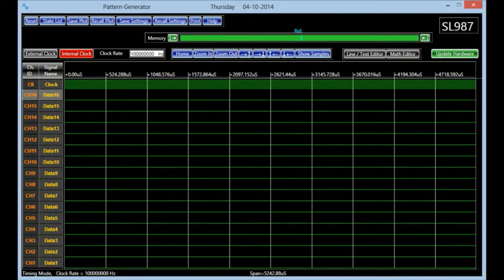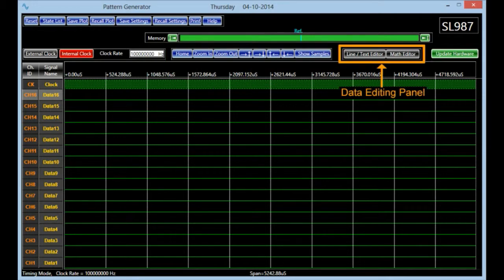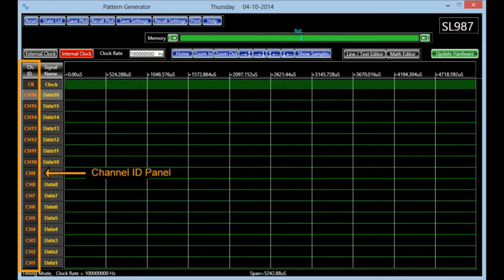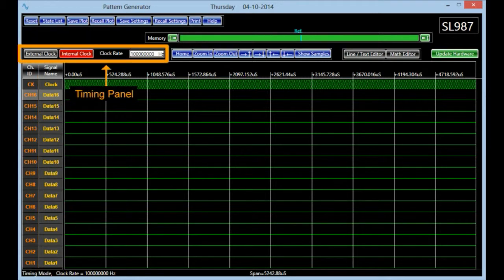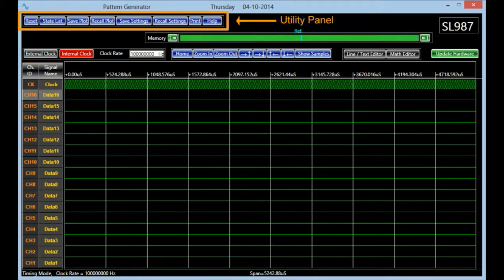In this instrument, the user controls are grouped together based on the function they perform. The display banner contains those controls which configure the screen plot. The data editing panel houses the controls used for bit editing. Besides these two panels, there are a channel ID panel, a signal panel, a buffer memory panel, a timing panel, and a utility panel. Each individual button in these panels allows the user to perform a unique task. There are other controls which are displayed only when they are called for. Together, they control the various features of the pattern generator.